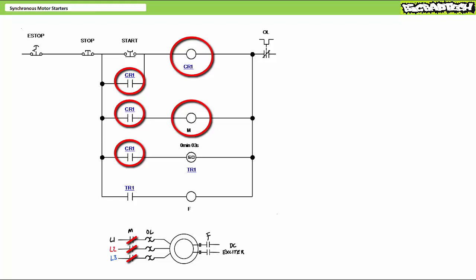Simultaneously, CR1 in rung 4 closes and energizes the coil of timer TR1 executing the on-delay, delay on energize, or slow operating function. As such, its associated contacts, notably TR1 in rung 5, remains open and the F coil remains de-energized. This being said, the clock is running, giving the rotor time to accelerate.